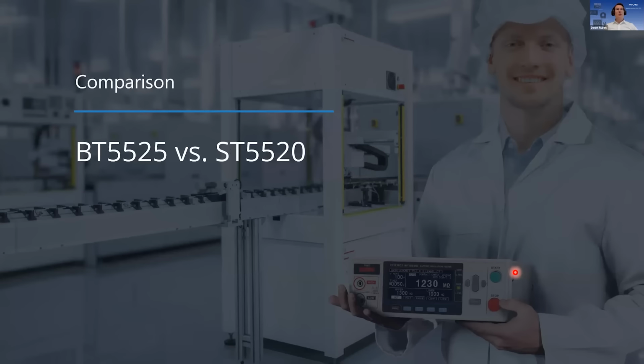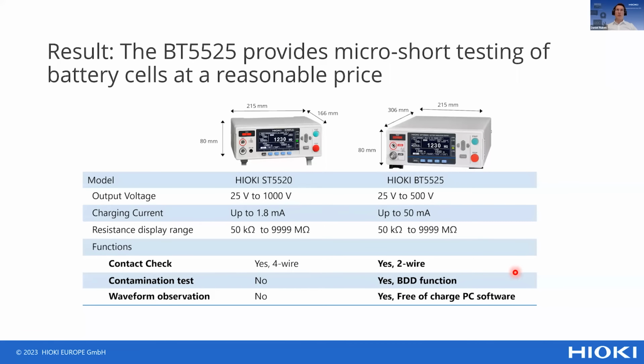As a last point, we want to give you an understanding of when a general purpose insulation resistance tester is being used, while the BT5525 as a battery insulation resistance tester is superior for your application. From the overview, you can see the test voltage of 1000 volt with the ST5520 is double the voltage, but for battery cells, you would not need anything higher than 500 volt to our knowledge, and therefore the 500 volt is completely sufficient. The difference in the application is that the parasitic capacitance of batteries requires a much higher charging current, and therefore the 50 milliamps will give you a faster charging speed.